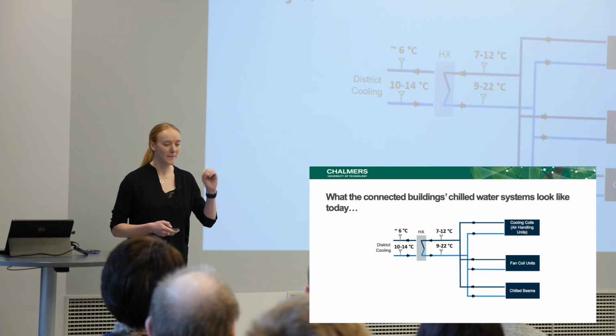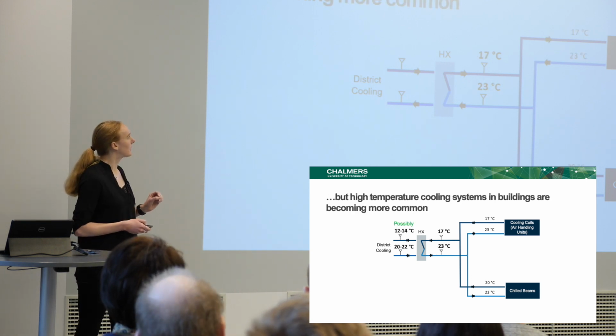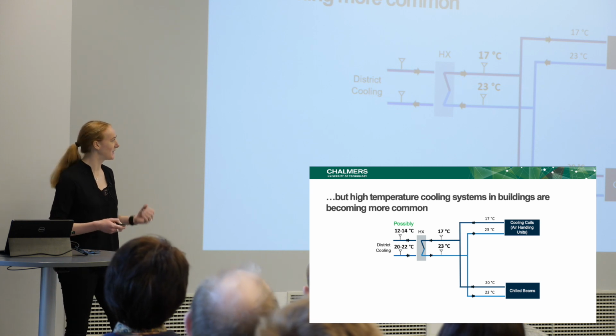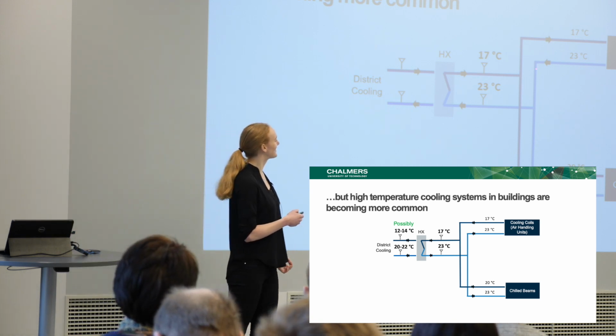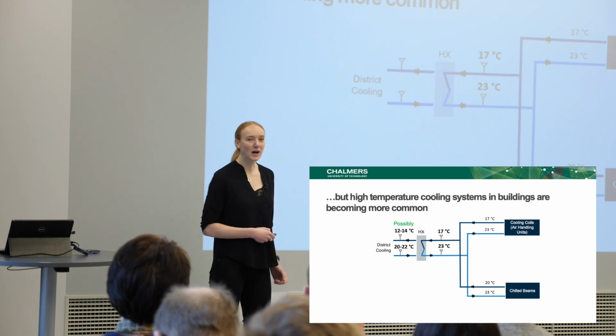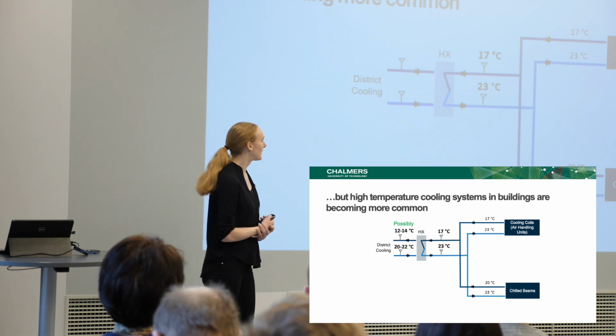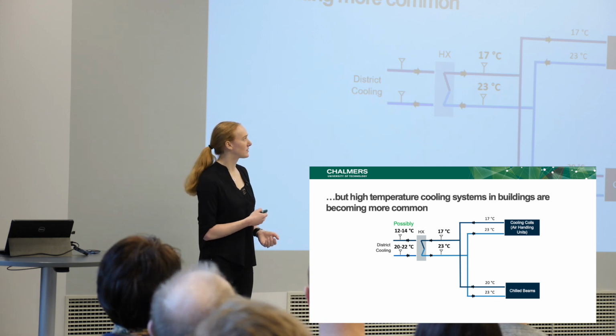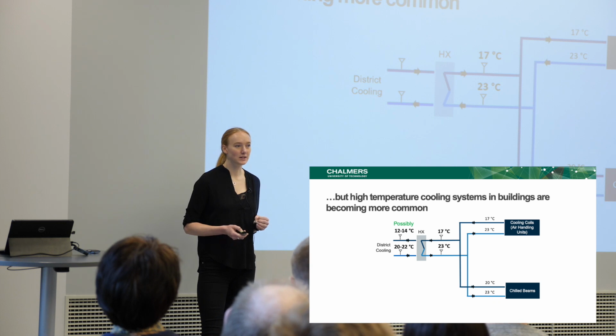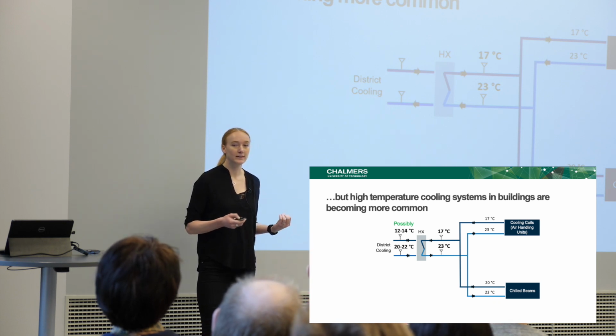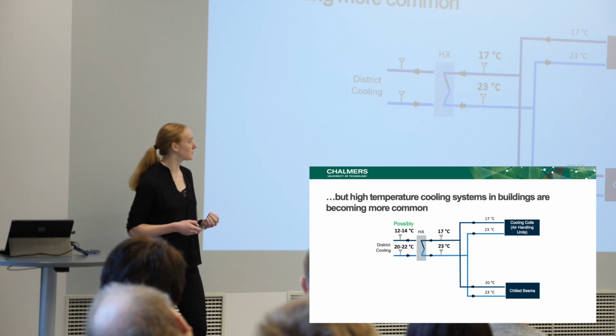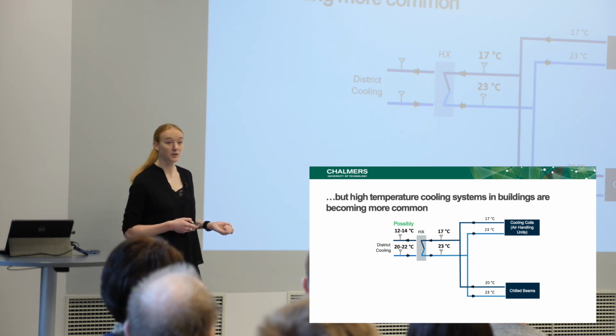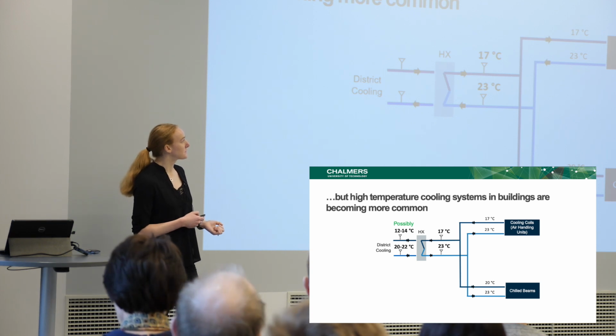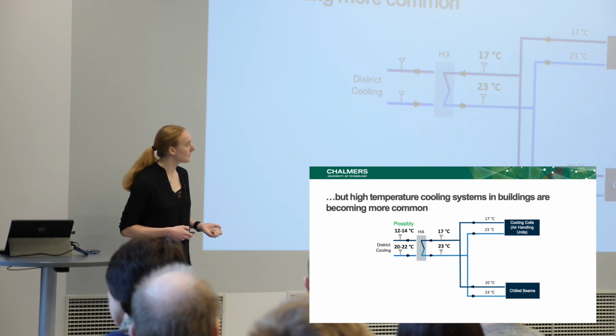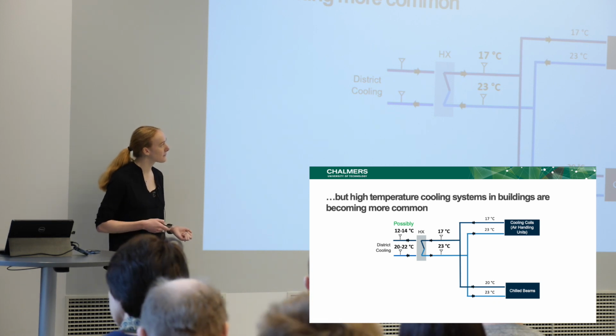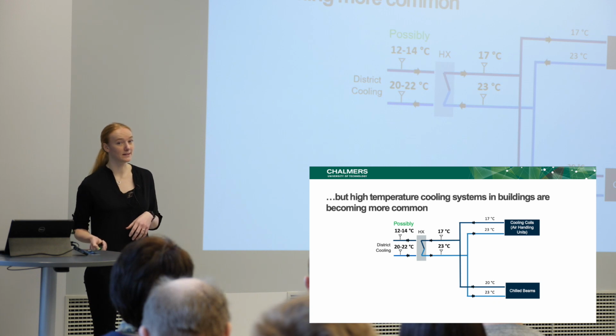But I also want to mention that the so-called high temperature cooling systems, which use higher temperatures, hence their name, are becoming more common in office buildings, because you can use higher temperatures such as 17 for the ventilation, depending of course on what the dehumidification requirements are for certain buildings. This has actually been installed in an office building in Stockholm. And they use 20 degrees for their chilled beams, and these together return around 23. So that opens up possibilities on the district cooling side.